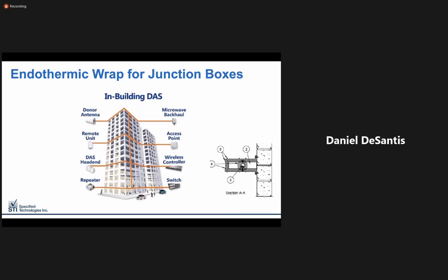When we're talking about circuit integrity and survivability requirements, it's not just the conduit that requires protection. Hardware housed in steel junction boxes, such as repeater cabinets or switches, must also be protected as part of the system. Having a fully encapsulated system is imperative to the performance of an ERRCS under fire conditions. It's only as strong as its weakest link, which is why we provide systems for various size boxes in different orientations. On the right, we have a typical steel box.